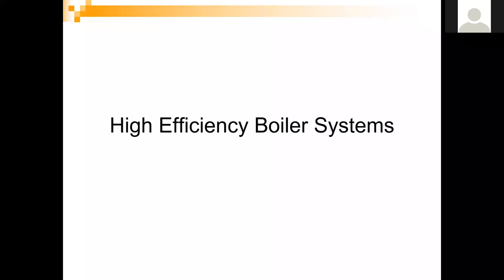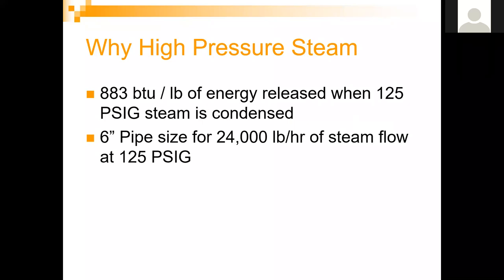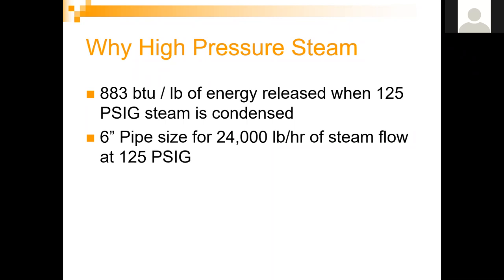We'll be talking about some of our high-efficiency steam boiler systems today. Why do people use high pressure steam? There are basically 883 BTUs per every pound of energy released when 125 PSIG of steam is condensed — when we go through that phase change from live steam back into water. A six-inch pipe can handle 24,000 pounds per hour of steam flow at 125 PSIG, so we can get a lot of BTUs through a six-inch pipe. That's why people use high pressure steam — to deliver a lot of BTUs to a concentrated area at high temperature, roughly 360°F at saturated conditions.